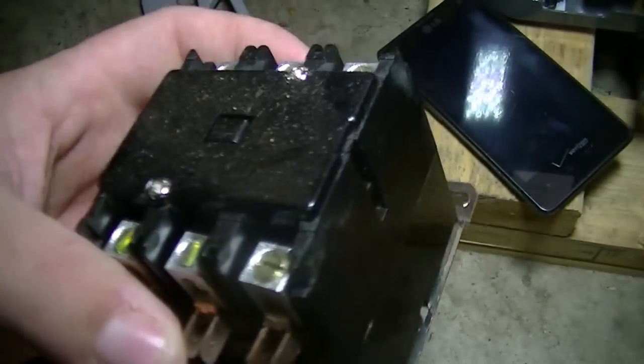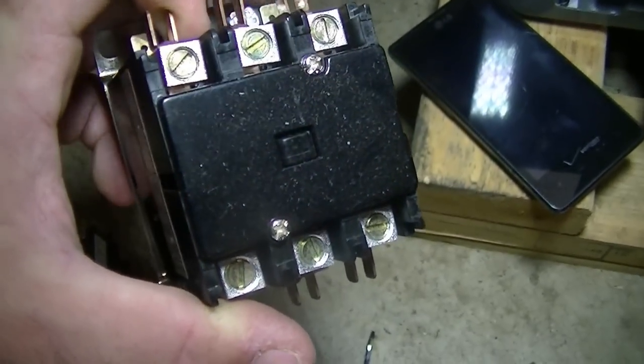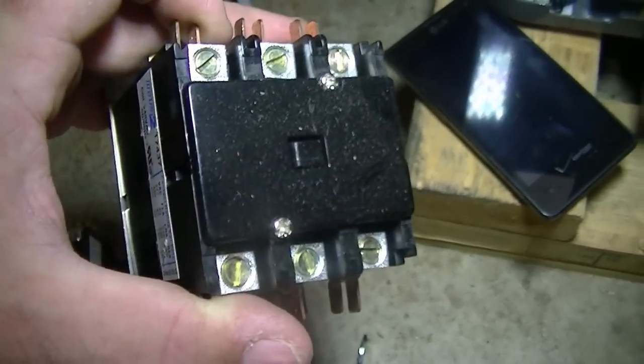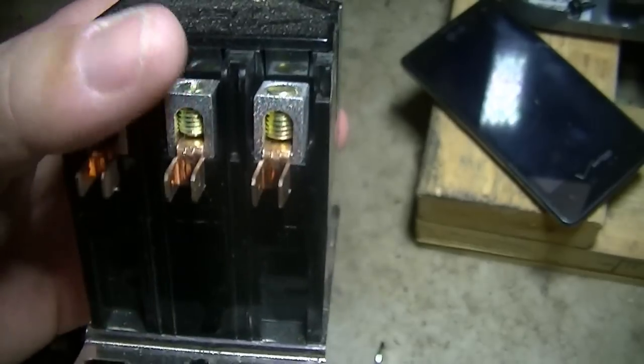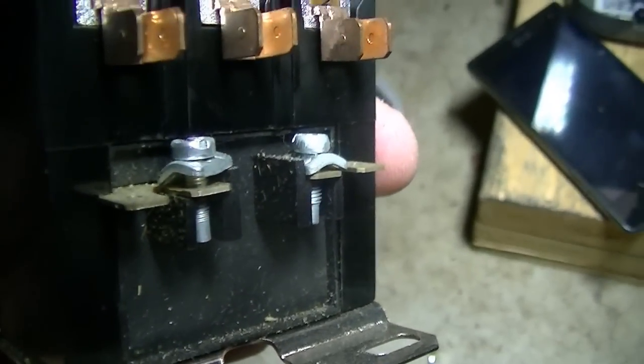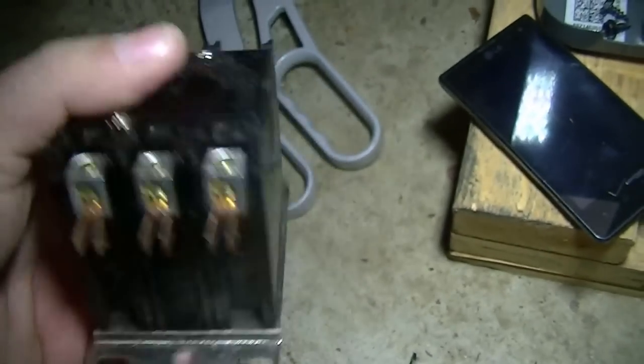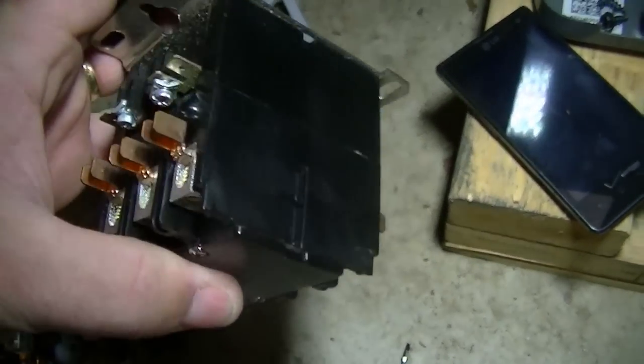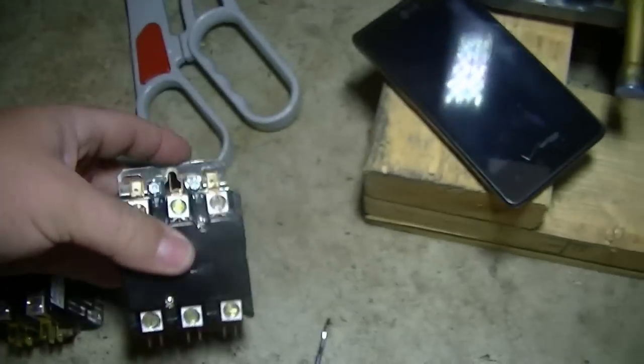Finally, in more commercial applications, you'll see this three pole contactor on your three phase stuff. Very similar. This one's a 24 volt coil, except you'll find this one on the end. It won't be on either side. And sometimes in commercial, the coils are different voltages: 240 volts, 120 volts. But this is just an example of a 24 volt coil.